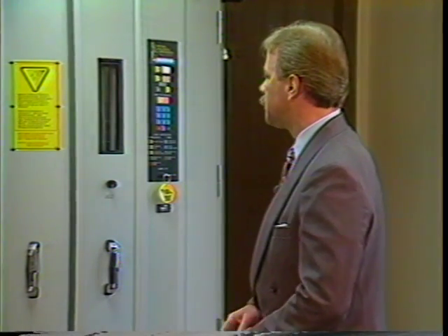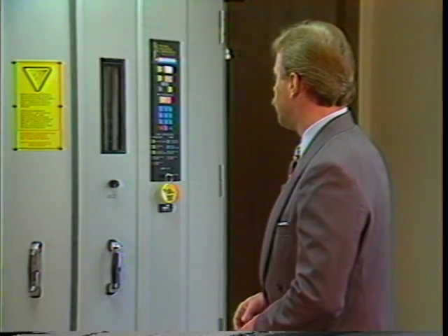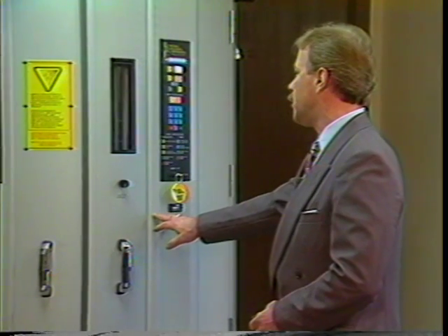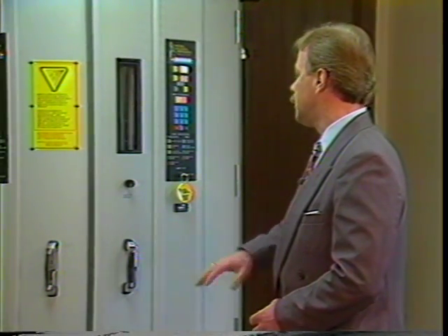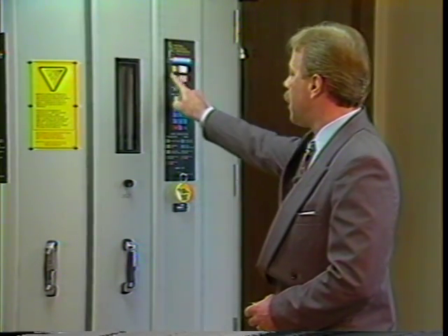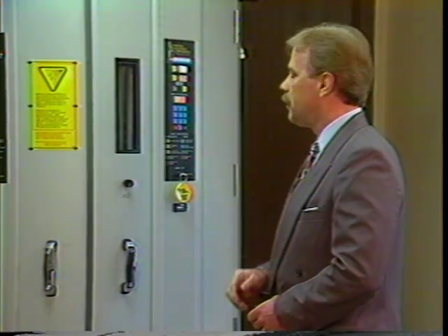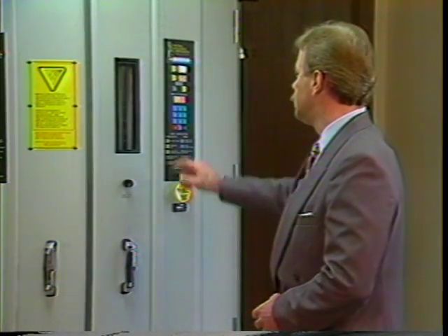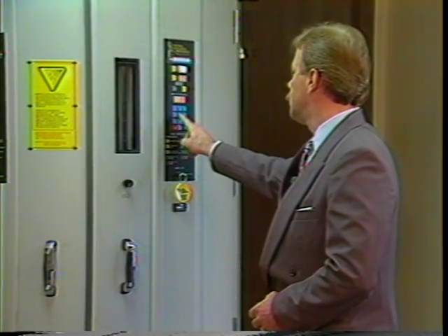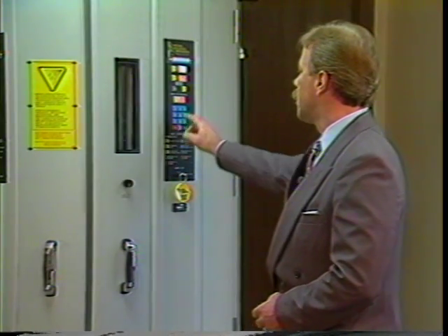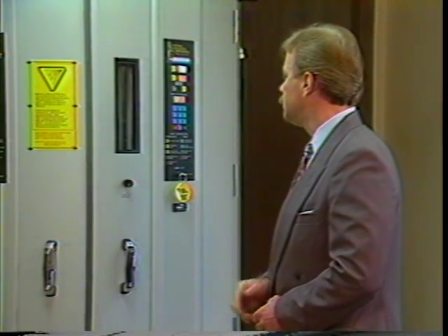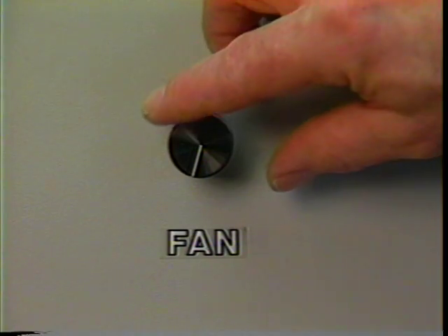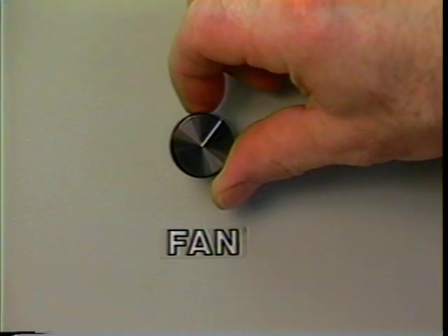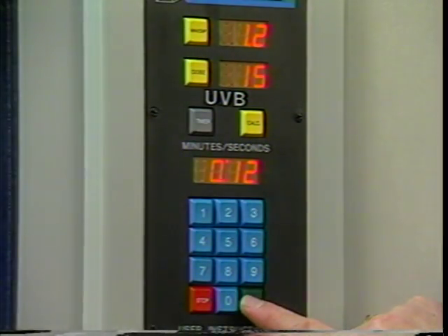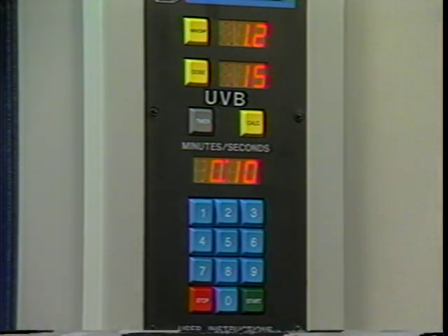Now, close the doors to the unit and you are ready to enter the information on the PhotoSense timer and begin treatment. Enter the appropriate information on the PhotoSense timer. That is, the readings from the lamp output, the dosage as prescribed by the physician, and calculate your correct treatment time. Turn the variable speed fan switch to the on position. Depress the green start button. The lamps will come on and the treatment will now commence.